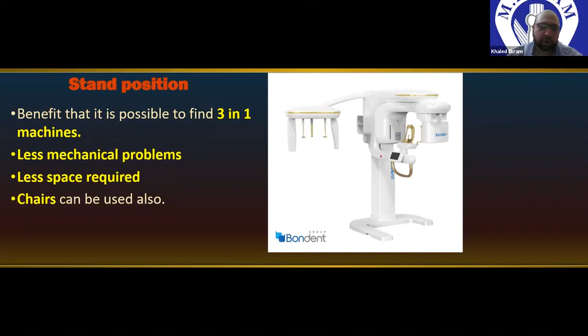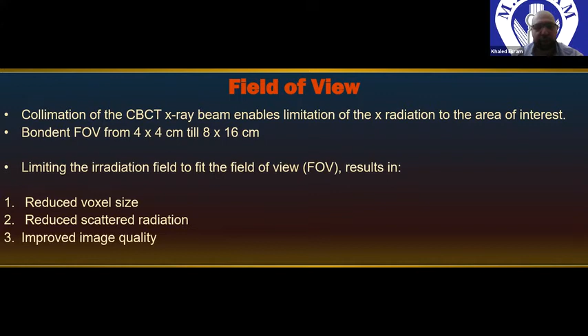So then we are speaking about the field of view. Field of view is the volume of the irradiated area. The field of view can be controlled by collimation of the CBCT X-rays to limit the radiation to a certain area of interest. So it's very important that the machine that we use has flexible fields of view to serve different specialties. As we mentioned in the beginning, for root canal cases, we need small fields of view like 4x4 or 5x5, not more than that. And also to be possible to scan large areas, as we see, areas to cover both jaws, or to cover even the whole maxillofacial area if we are talking about a hospital or a government institute. When the field of view becomes less, this means better resolution, less voxel size, and improved image quality due to less scattered radiation.